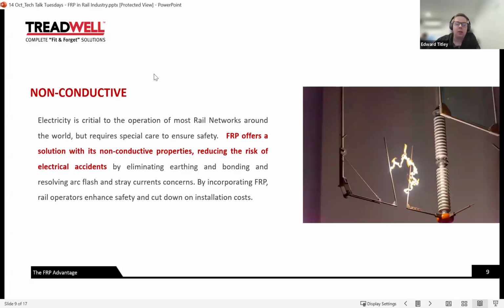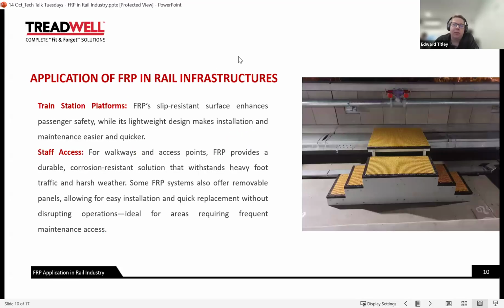I had feedback from a client a while back who was looking at an FRP fence for their substation instead of traditional chain mesh fencing. They said the cost of the fencing was one aspect, but the earth loop in the ground around the fence, to allow it to be earthed and bonded, actually costs more than the fence itself. So there are cost savings, time savings with the install, and improvements in safety, given there's no risk of the structure having stray currents become live and giving someone a tingle or an injury. So that's another benefit of FRP.